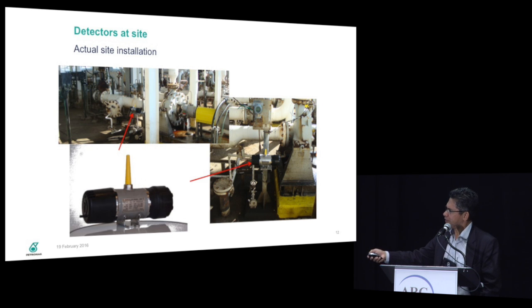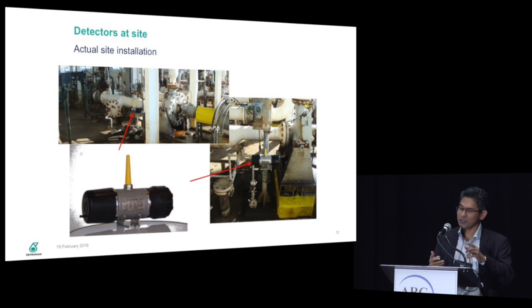Just to briefly explain, the gas detector is using infrared technology. To preserve the battery, they have built-in acoustic sensors. These acoustic sensors are on continuous monitoring. Whenever there is a gas leakage, they will hear the sound, and by the sound, they will trigger or wake up the infrared sensors. So the infrared will start doing the sensing. That's how the technology of these wireless gas detectors works.